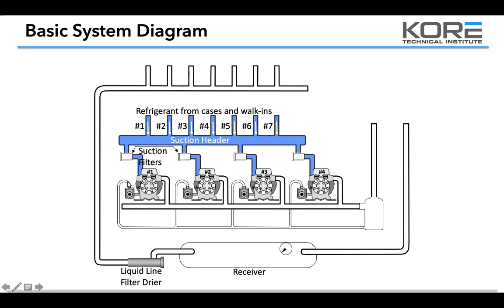When compressors short-cycle, it doesn't fling the oil around and keep the oil warm inside the crankcase. They want to get some good run time so when they bring that first stage on, that compressor runs, gets nice and warm, and gets the oil slinging around for good lubrication. Short cycling is really hard on the electrical as well as the compressor itself. When you're trying to balance a rack, look at your cycle times, look at your PID control strategies, and make sure you're seeing good even staging.